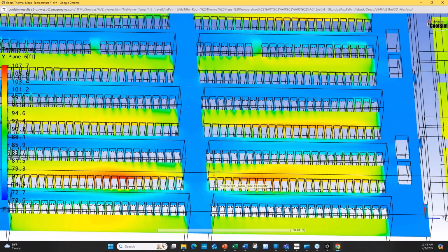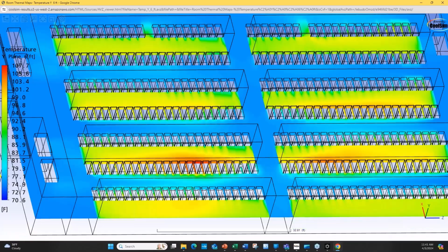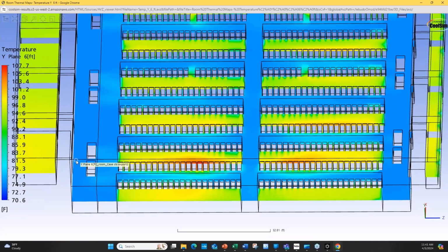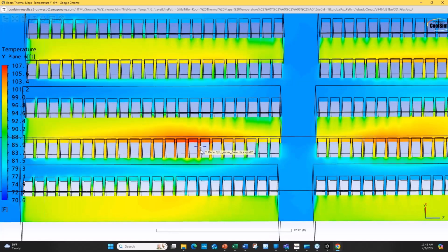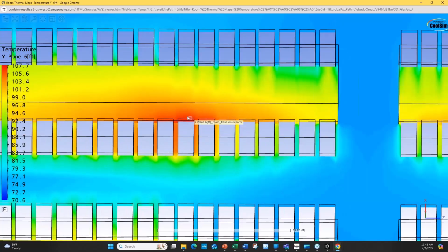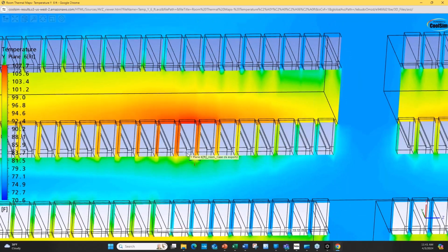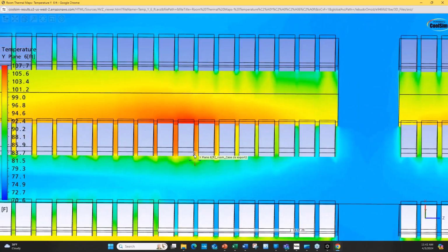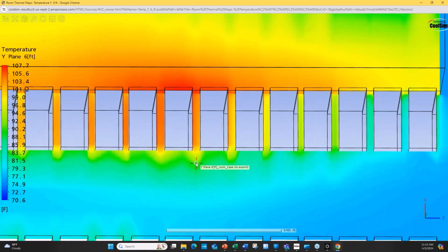And by the way, this will happen also in other cases where you get a pressure differential. For example, if you have the chillers go down or fans go down on the air handlers, you'll get a pressure differential and it'll come leaking through. And the leakage often occurs here. And what I find sometimes is that the people I'm working with, Magnus, are the design community and not the people doing the IT implementation.